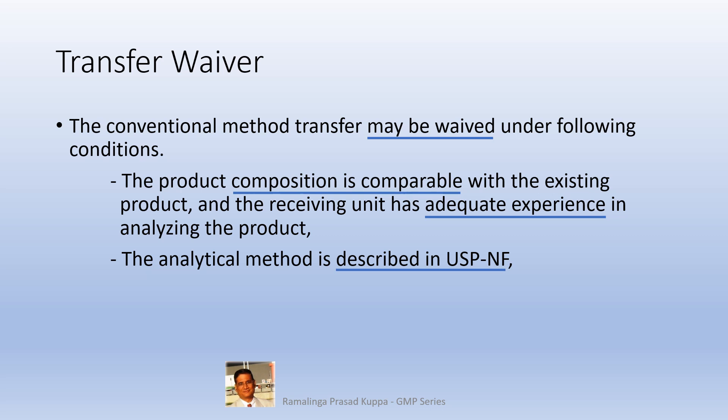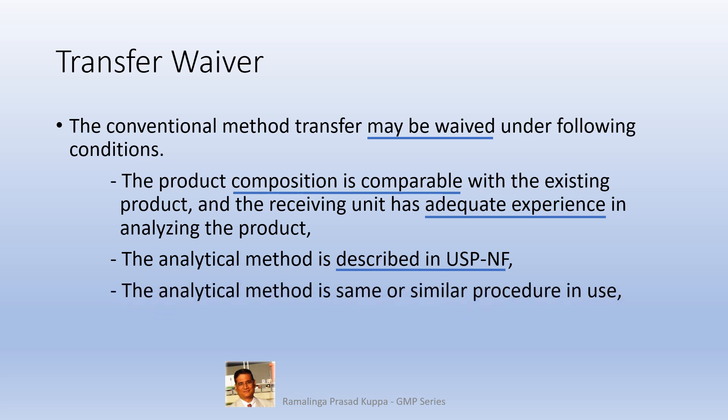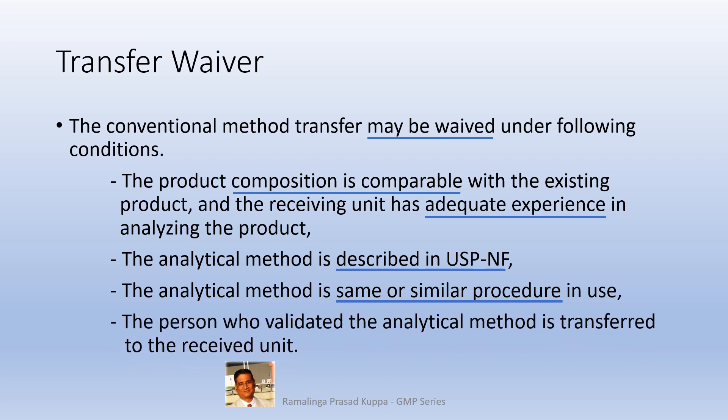However, it is necessary to carry out verification of the test method as per USP 1226, which can be understood conceptually as limited or partial validation. A waiver is also applicable when the analytical method is the same or similar procedure already in use at the receiving end, or when the person who validated the analytical method is transferred to the receiving unit.